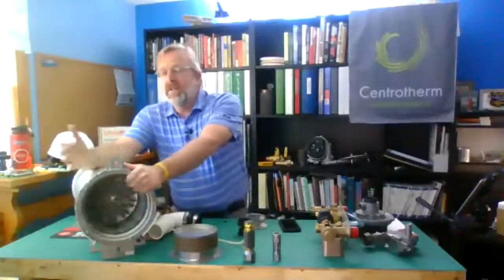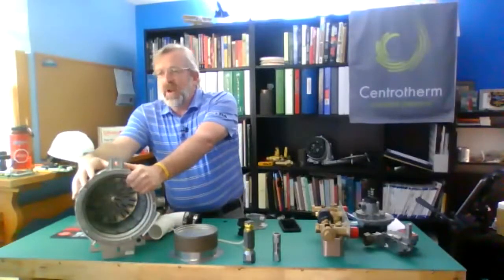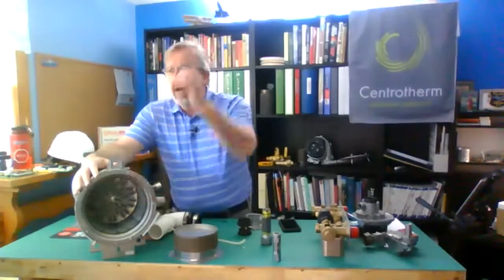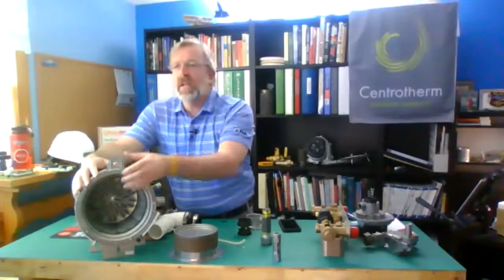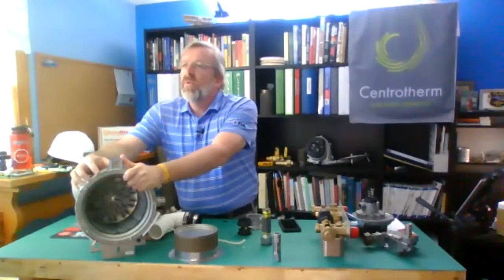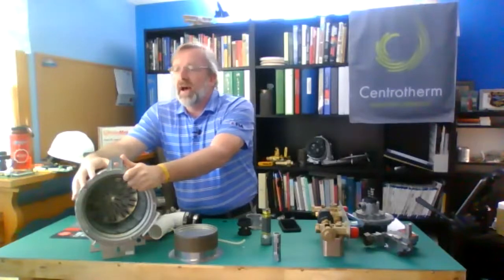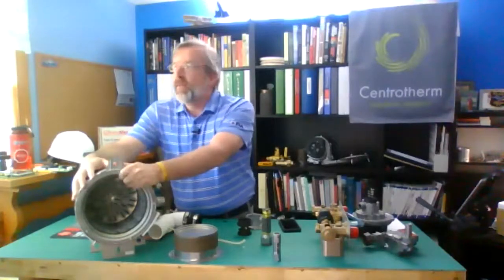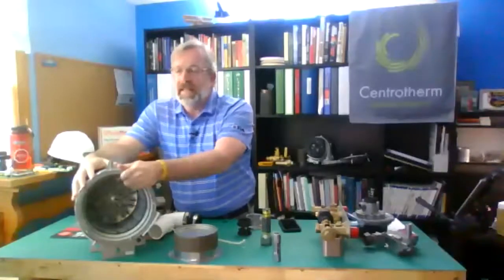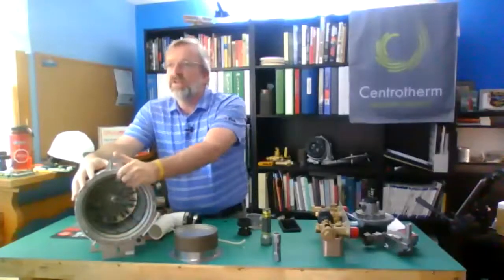While I've got that open, if it's dirty and I want to clean it, I'll get a look in there, so I can give you an idea of what that looks like. This has got a little scaling on it right here around the sides. It's not bad. What I would do in here is spray vinegar and water. And the vinegar is going to depend on what territory or area you're in. Up where I am in the Merrimack Valley, head over to Market Basket and just get some distilled white vinegar.